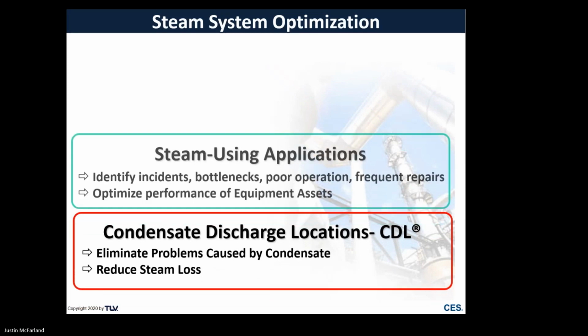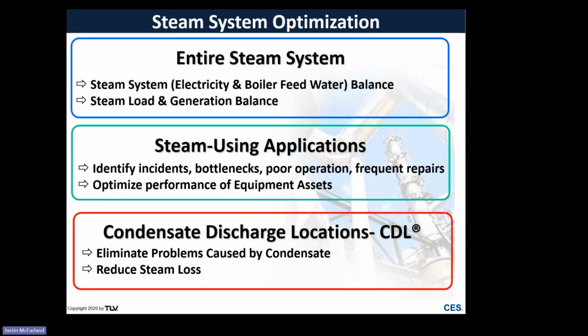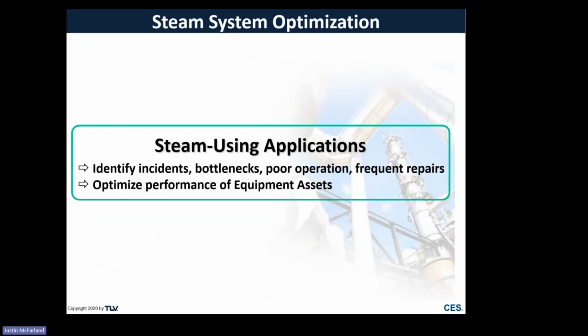So when it comes down to steam system optimization, TLV sees this as a three-phase approach, where looking at condensate discharge locations, and if you're able to have a good, healthy steam trap population, that will, in my experience, and probably anybody else's in TLV's experience, probably fix 90% or more of the problems that our customers see on site. Today we're going to be talking about steam using equipment, so primarily with identifying incidents and bottlenecks, poor operation, and optimizing performance of those equipment assets.